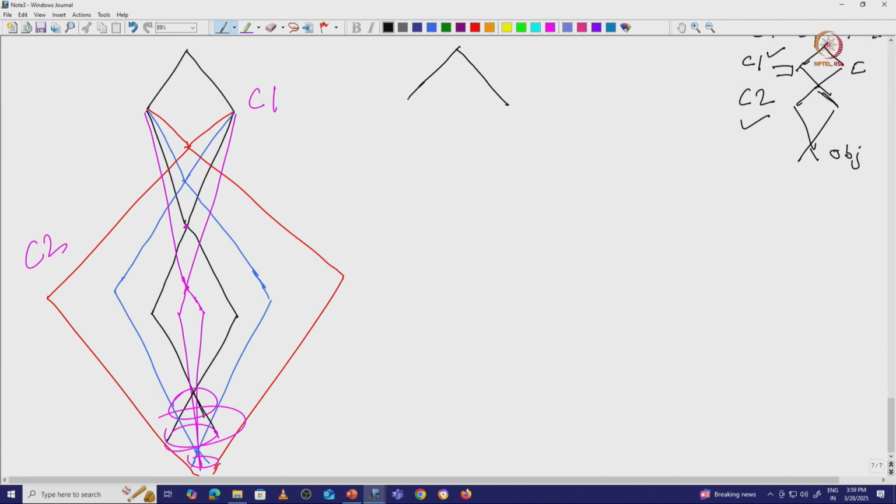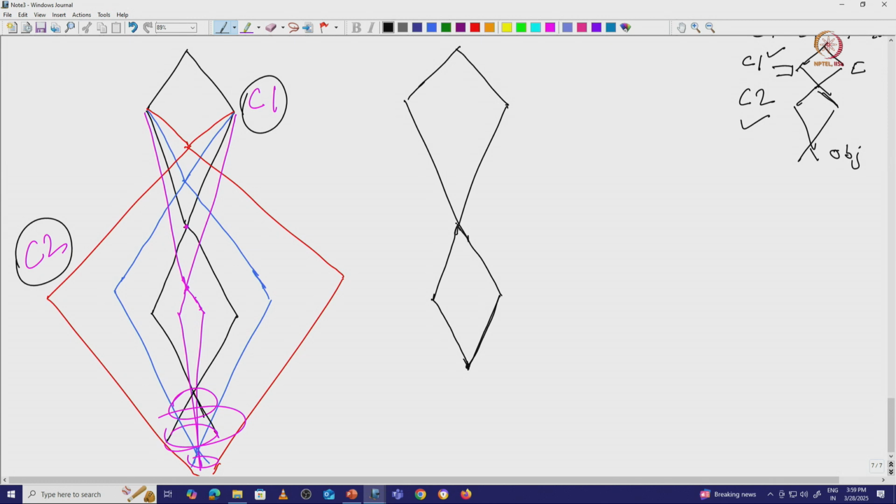So rays come to the first crossover point, then go through the C2 lens, and now we fix this particular point. It does not matter; we will use a magnetic field in such a way that all the rays go through this point. So we are changing the C1 lens current and C2 lens current simultaneously in this diagram, but this point is fixed here. Now, let the rays go and give us an image.